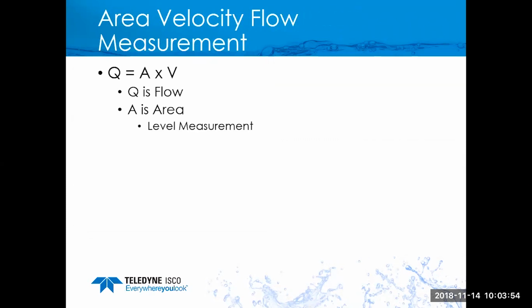All right, so let's talk. Today we're going to be talking about area velocity flow measurement. We're not going to be talking about flumes or weirs, but focus mainly on this. Q, your flow, is equal to the area of water. We find the area by doing some sort of level measurement. We'll either use a pressure transducer. In the case of a 2150, we use a pressure sensor, but you can also use ultrasonics. For the ultrasonic sensor, there are a couple types. One is downward looking, and you can also have an underwater upward looking ultrasonic to measure that level.